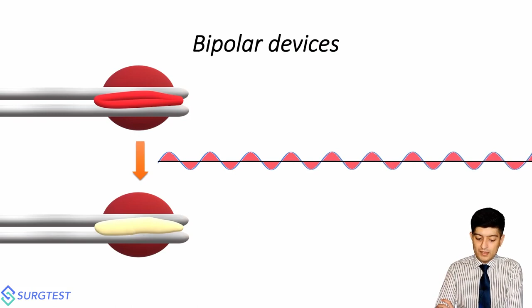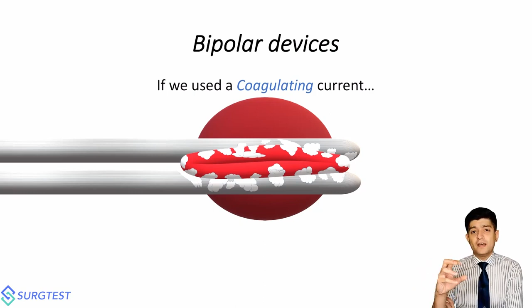If we land up using a coagulating current for whatever reason on a bipolar device, this is what is going to happen. Because of the high voltage nature, there are going to be several small eschars, like the video that I showed you, forming all across the vessel. Now, these caramelized eschars are by default going to be sticky. So when you open up the two prongs of the device, the vessel is going to essentially stick to them and it's going to prop back open.